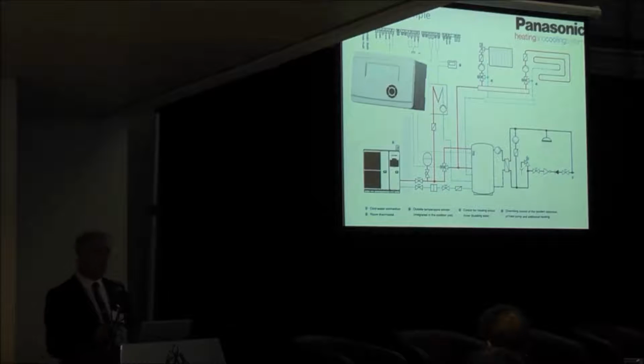Okay, obviously, this needs to be designed, as our friend from Kingspan mentioned earlier. This needs to be designed into the product, into the installation from day one. The thermal store has to be the correct size, the buffer vessel or whatever you're selecting has to be the correct size, your cylinders have to be the correct size. There's no point in investing in this technology if you have a 200 litre system or even a 90 litre buffer. You're heating 90 litres of water up to 80 degrees Celsius. Okay, that's fantastic. You turn the radiators on, you have loads of heat all over the house, but 90 litres of water will just be gone in no time.